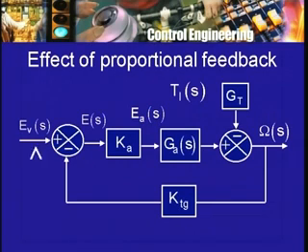The applied voltage is not obtained now directly, but I obtain it by having what I have called a reference voltage. Then there is this difference device which takes the difference between the reference voltage and the feedback voltage. The feedback voltage in this case is simply the tacho generator coefficient, EMF coefficient multiplied by the speed. This difference is then sent through what is effectively an amplifier, and we have called the gain of that amplifier Ka. In the Leonard type of speed control, this Ka is represented by something which is not that simple.